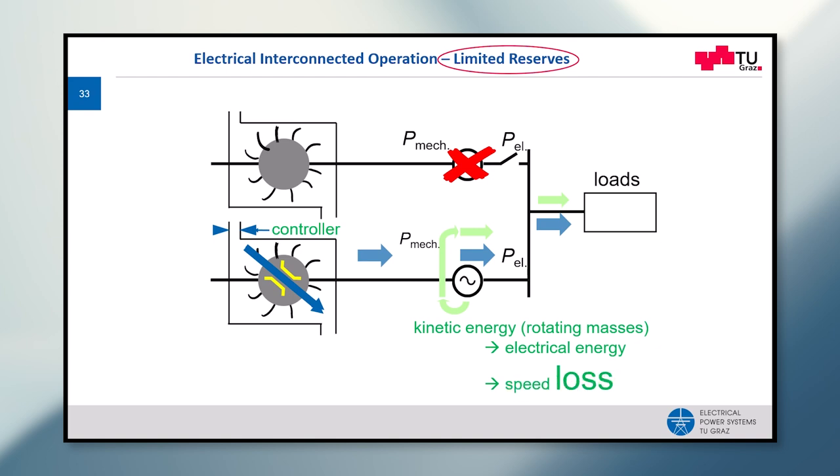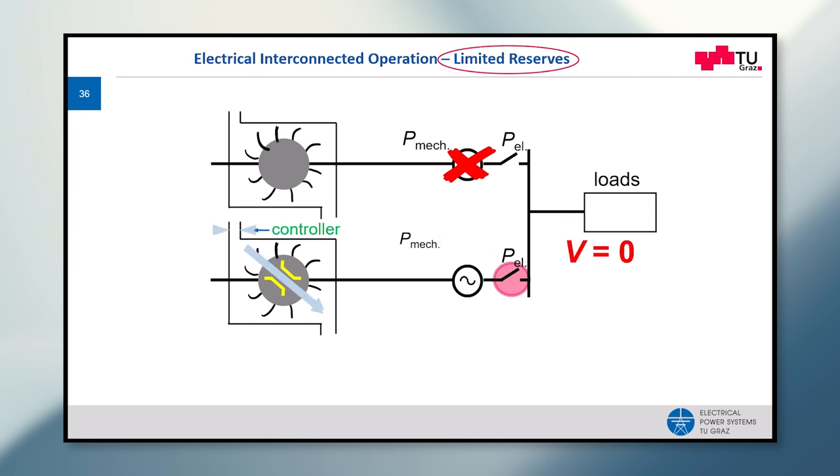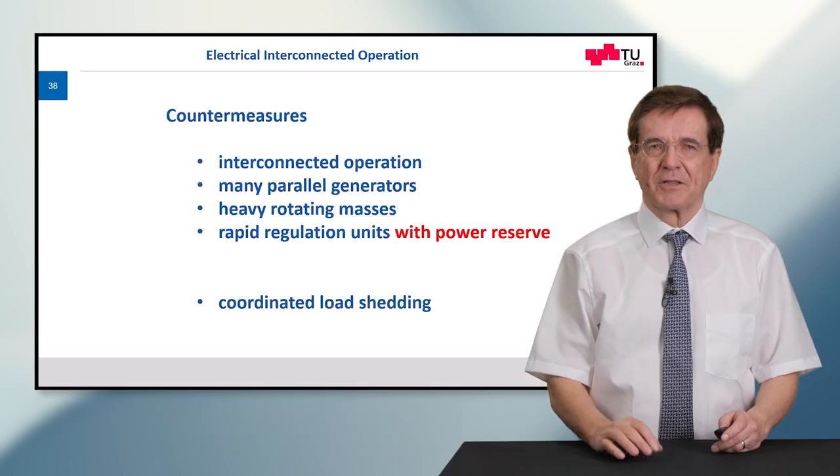This means the power plants go into self-protection and they trip out and separate themselves from the grid. Now once an under frequency trip has happened, you see the last remaining circuit breaker has opened. There is no voltage provided to the loads, and this is a blackout.